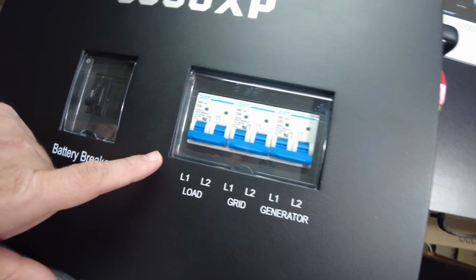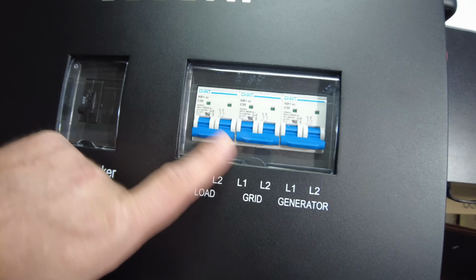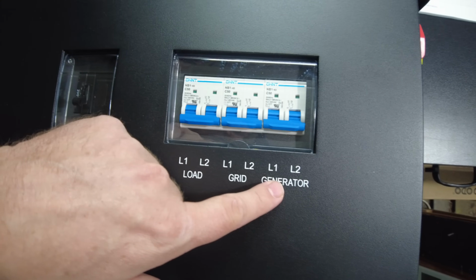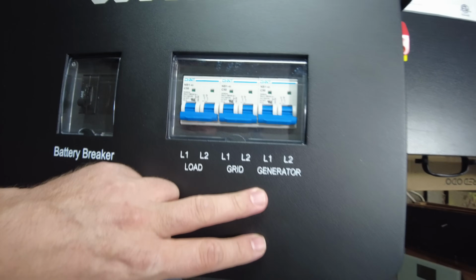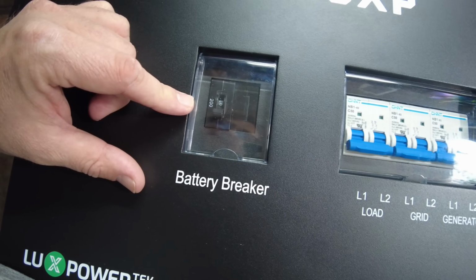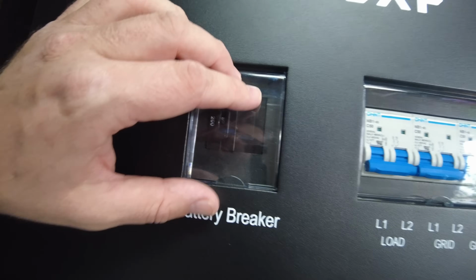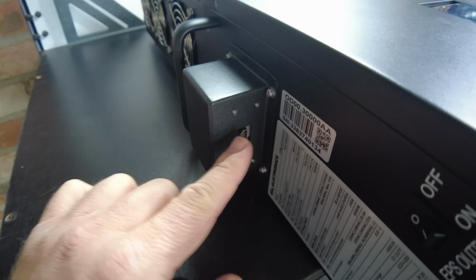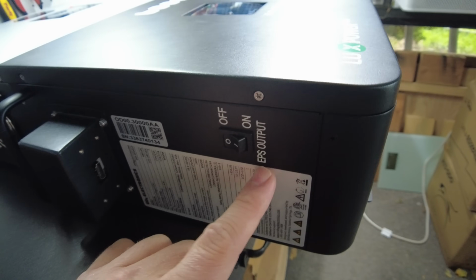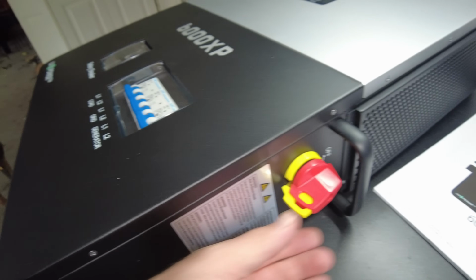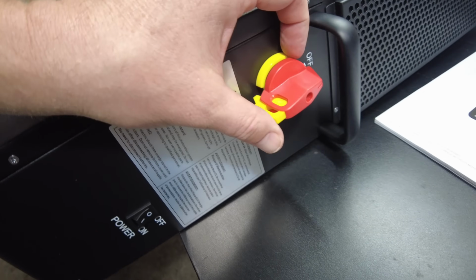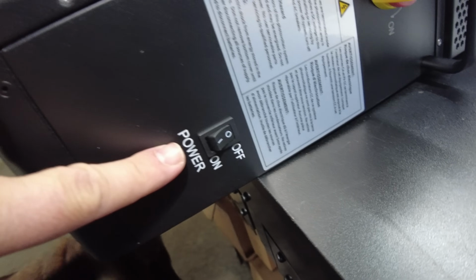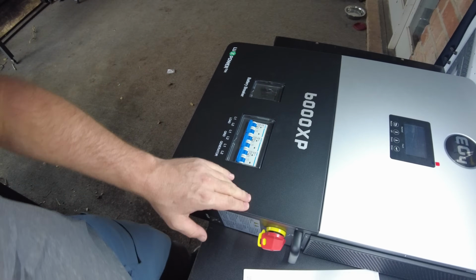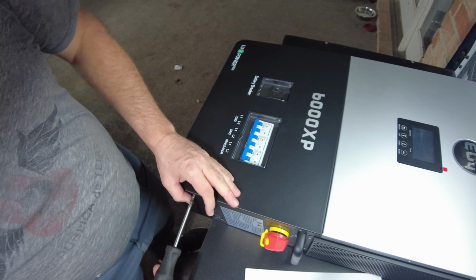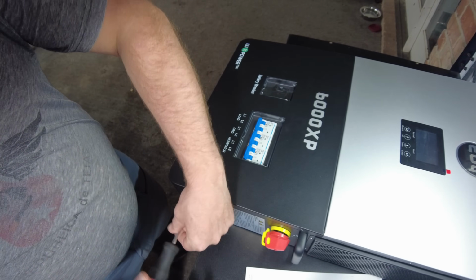Okay, look here, we've got our load disconnect, we've got grid, and we've got a generator disconnect. And we also have a battery breaker, looks like 200 amp. We've got our display here, we got the connection for our Wi-Fi dongle. EPS output, I'm not sure what that is, but we've got an off-on switch for it. And then on this side, it looks like we've got our PV disconnect. And then we've got a power switch. So let's open this panel up here and take a look at what's on the inside where we're going to wire things up.